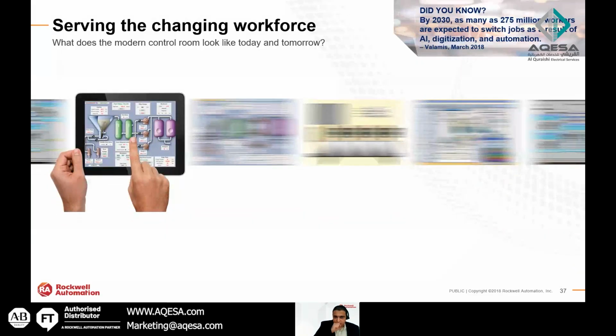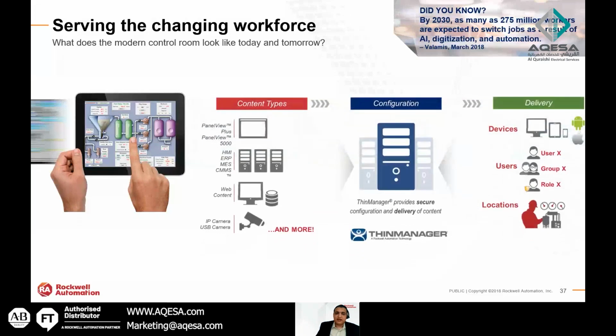Going to the Thin Manager: it's a solution that handles contents like Panel View Plus, Panel View 5000, HMI, ERP, MES, CMMS, whatever web contents, IP cameras. All you need to do is configure the Thin Manager server to take all the information from all these software and deliver it by device, by user, by location. If you are in a different location, you can see different information. If I'm in this chemicals building, I need the SCADA and the HMIs, and if I'm an engineer, I need the programming inside this building. So based on who is logging in, where, and which device is being used, you can choose what contents to show.